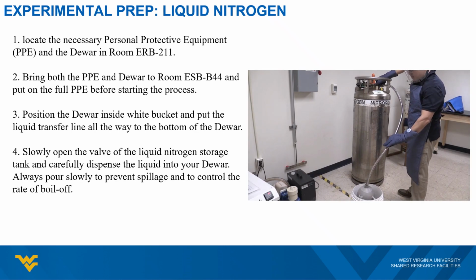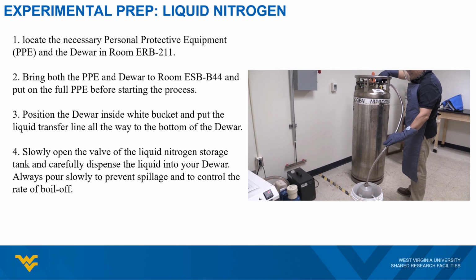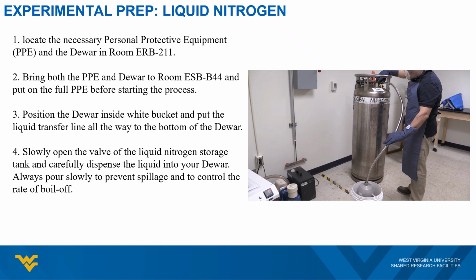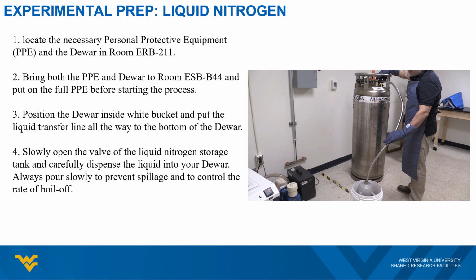Once everything is set, gently open the filling valve of the liquid nitrogen storage tank. Carefully dispense the liquid into your dewar. Ensure to pour slowly. This measured pace is essential both to prevent any spillage and to control the rate of liquid nitrogen boil-off.